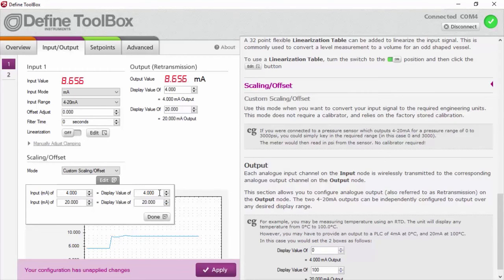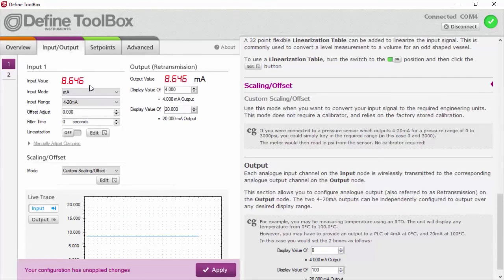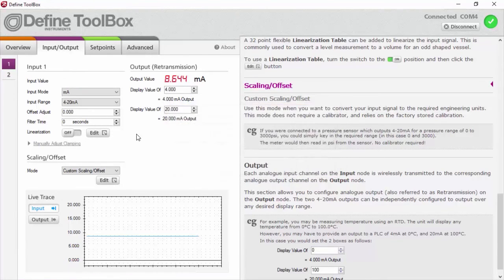But from my data sheet, I know that my sensor at 0 psi will output 4 milliamps, and at 15 psi will output 20 milliamps. So I could put in 0 and 15 here, and I would get the input value coming up in psi, but it'd be better if I can actually put in feet. So 0 psi is going to be 0 feet, and if we look up for water, 15 psi is 34.6 feet. So if I now click done, that 8 milliamps, once I click apply, will be translated into feet. So that's now 10.03 feet of water from the bottom of the tank.